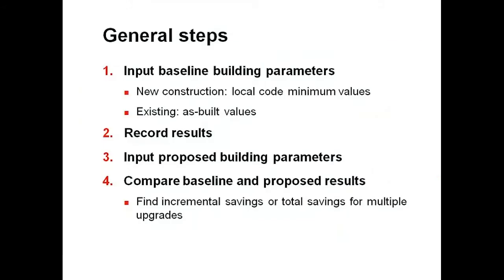What are the general steps for using the Back of the Envelope Calculator? Step one is to input your baseline building parameters. For new construction, that usually means inputting the local code minimum values. For an existing building, that means finding the as-built values and entering them. Once you have your building baseline established, record the results for later comparison. Then step three is to input the proposed building parameters — what upgrades are you willing to make, and how will they affect the resulting energy and cost? Record the proposed building results and find the incremental savings between the baseline and your proposed. You can look at individual measures or a host of measures to see how multiple upgrades affect building energy use.